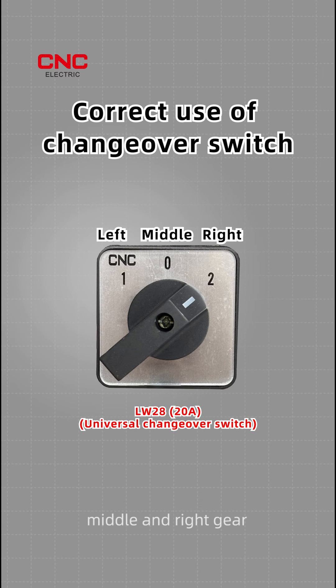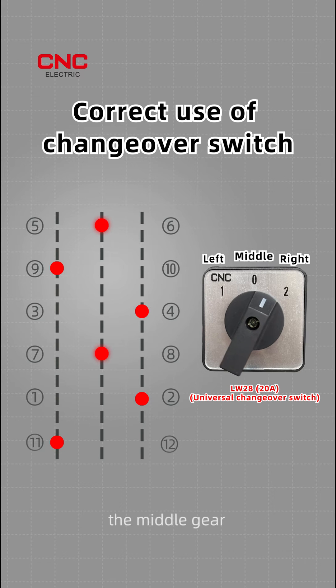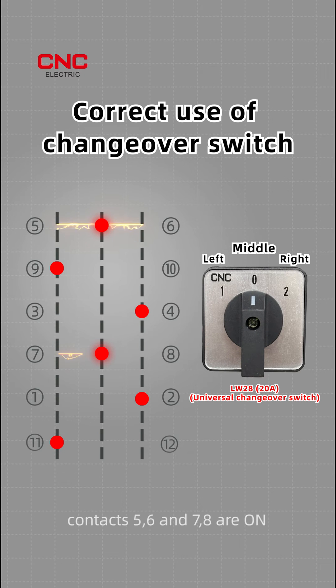This is the three-gear changeover switch with left, middle, and right gear. There are two red dots in the middle gear. When the switch is turned to the middle gear, contacts 5, 6 and 7, 8 are on, available as manual mode.